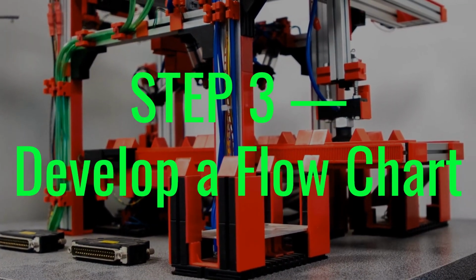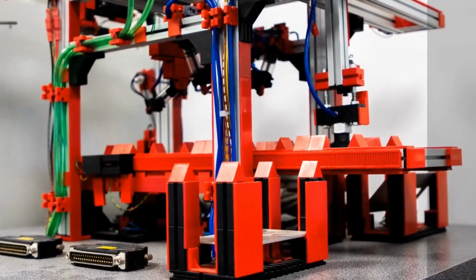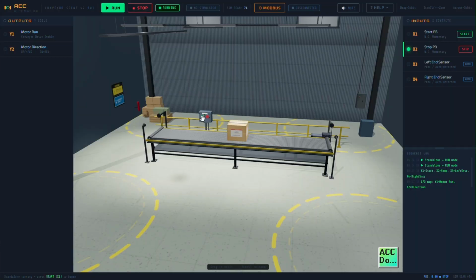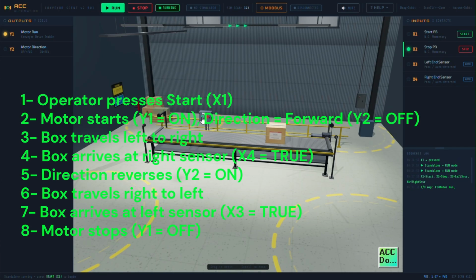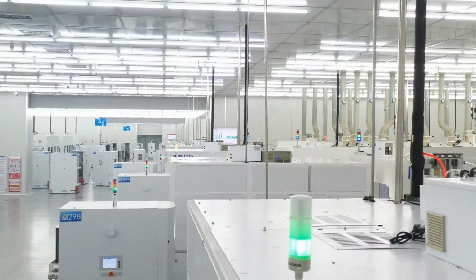Step 3. Develop a flowchart or sequence of operations. Map out the sequence of operations. First, the operator presses start. The motor starts with the direction set to forward. The box travels left to right. The box arrives at the right sensor. The direction reverses. The box travels right to left. The box arrives at the left sensor. The motor stops. The system is ready for the next cycle. The stop button can interrupt the motor at any point and immediately stop it.